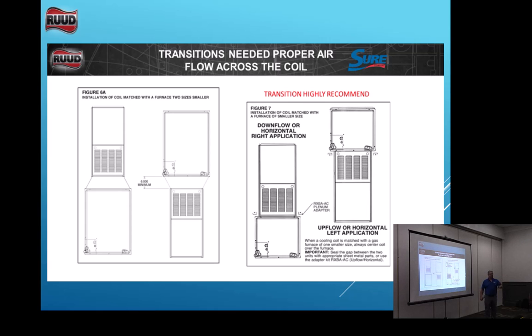So we really need to talk about starting to use transitions. I would on every change out, even if it is the same size furnace and coil. You need that air to straighten out and become linear before it goes through that evaporator coil, so it works most efficiently. So I would tell you that you really need to get in this habit of using transitions, okay? Because a lot of times it solves a lot of problems. You know, they're worth it.